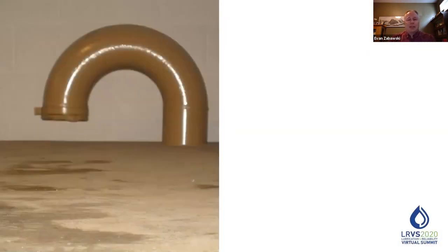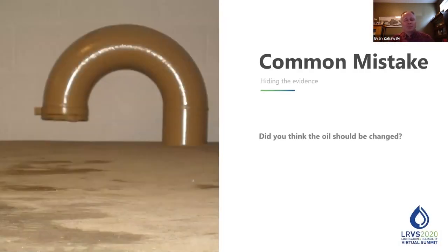Another common mistake is, are you focused on the symptoms? Are you focused on things like wear metals? Because wear is a symptom. Something is making it wear. Is it a misalignment? Is it an imbalance? Something has caused it to wear. So why are we focused on the wear? That's a very common mistake, that people are just looking at that and making all their judgment based on the symptoms, not necessarily looking for what on the report tells me the true cause of all that wear.